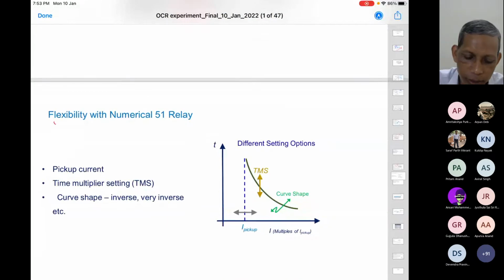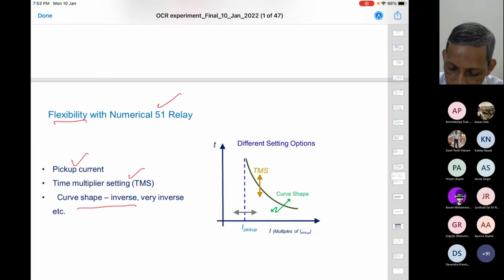So what is the flexibility with the numerical 51? 51 means IDMT characteristics. You see here, three things are there. One is the pickup setting, which we can change. You can change the TMS, and you can change the curve shape, very inverse and so on. If you make TMS 0.1, the curve will go down. If you give 0.3, it will go up. That is one option. Pickup: if you shift the curve to this side, the pickup is reducing. If you go to the right-hand side, the pickup is increasing.